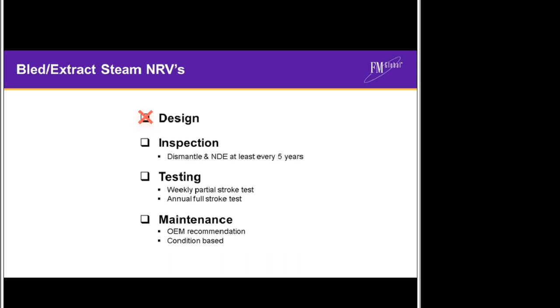It is unclear what the reason for this is, but FM Global clients, including those operating turbines in the sub 100 megawatt range, have suffered losses due to malfunctioning non-return valves, leading to overspeed and overpressure events. As with ESVs, provided all risks have been minimized on the turbine, FM Global recommends a full internal inspection at no more than 5 yearly intervals. However, if there are relevant deficiencies such as water chemistry excursions or intermittent testing, a higher frequency would be recommended. Similarly to ESVs, maintenance should be completed per OEM recommendations or as conditions determine.